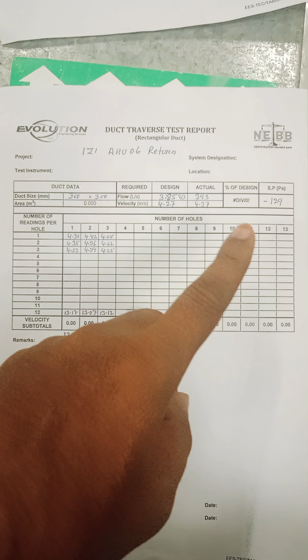This is the static pressure, okay, and this is our number of readings for each hole, okay. Now in total we get 103% for the supply duct traverse. This one is for the return duct traverse. Duct size 300 into 300. This one is required, this one is designed, this one is actual, this one is the static pressure in the duct. The number of holes is 1, 2, 3 and the reading for each hole is 3. The total number of readings is 9.